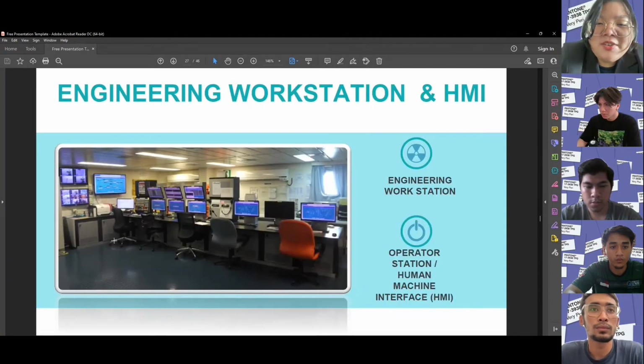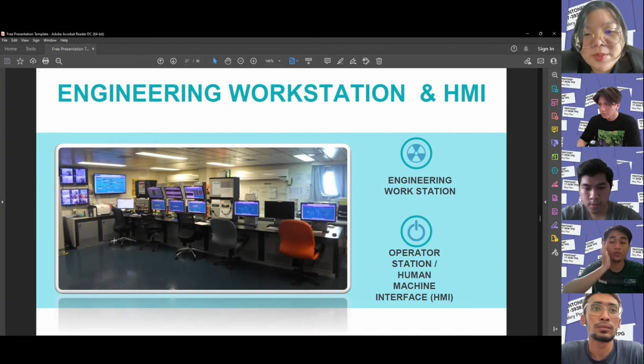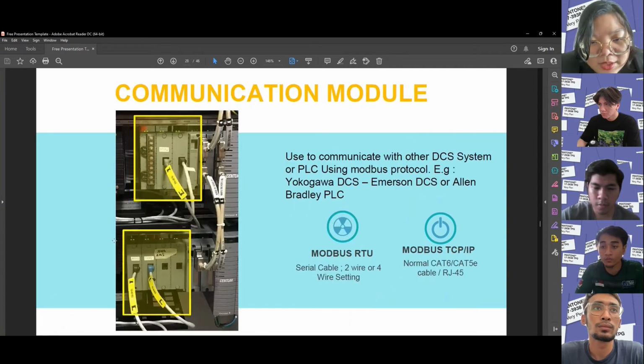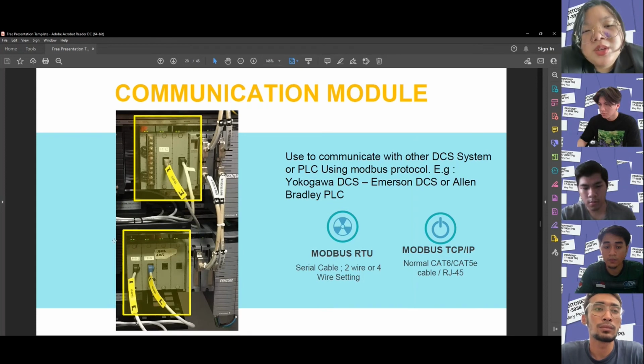Okay, engineering workstation and HMI. This HMI consists of two types. The first one is the engineering workstation, and I will also explain about the operator station or human machine interface, which is HMI. Okay, communication module. This communication module is used to communicate with other DCS systems or PLCs using the Modbus protocol, for example Yokogawa DCS, Emerson DCS, or Allen Bradley PLC.